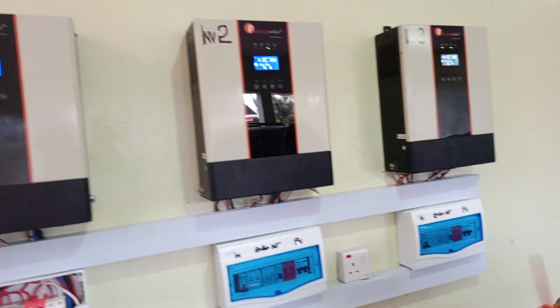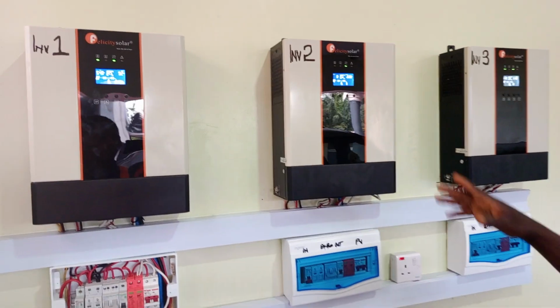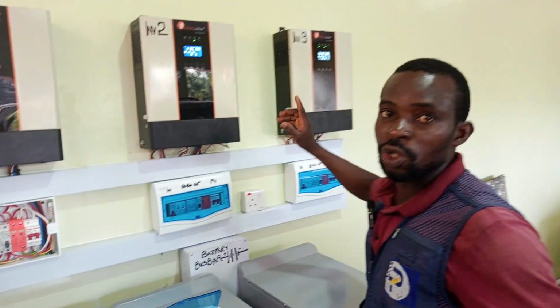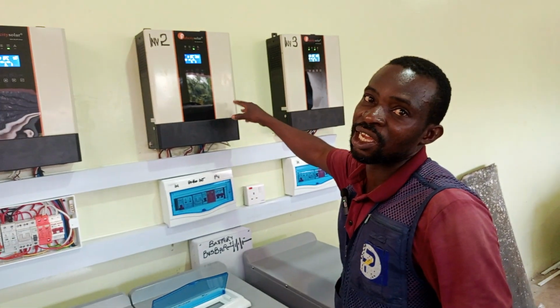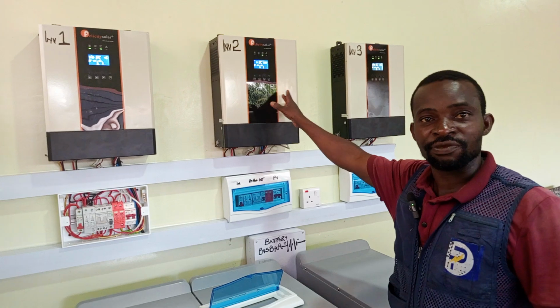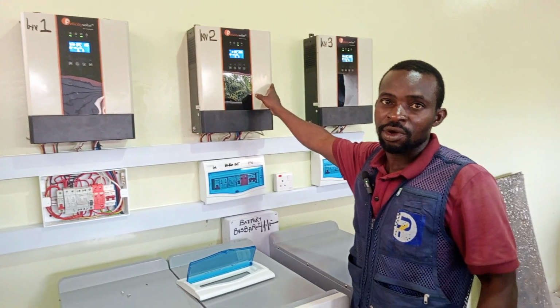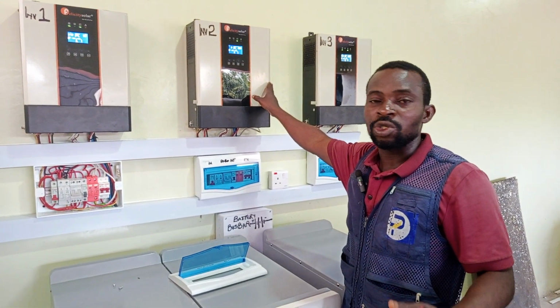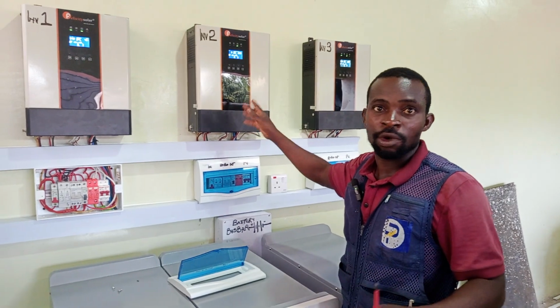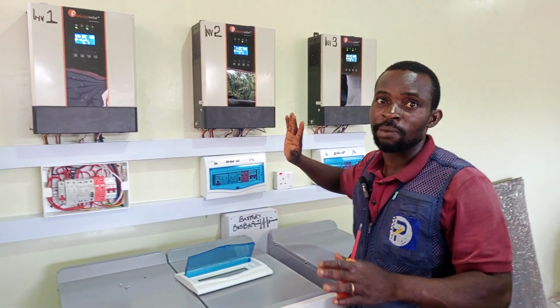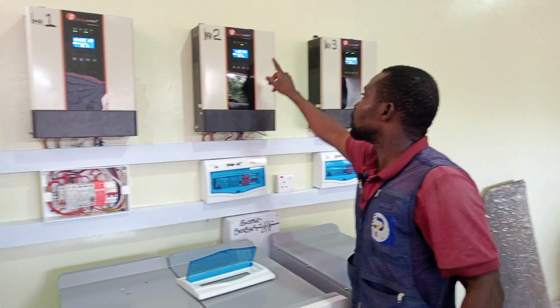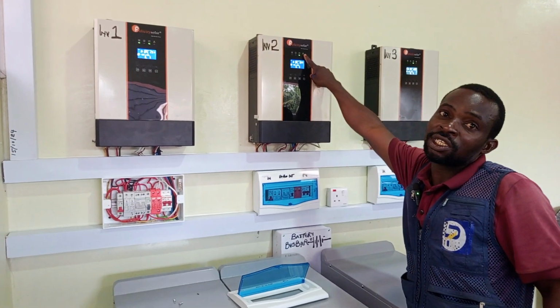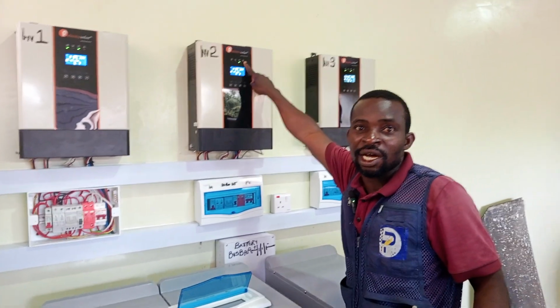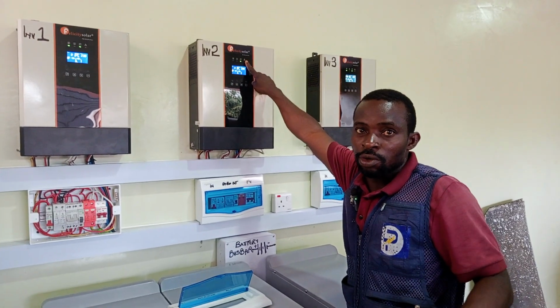But one disadvantage is that, let's say as you are running it, if there's still load and you only turn one on, and the load is more than the inverter can handle, it will show you error 45. What you need to do is restart your system, turn off your load and restart. Everything will come back to normal. So don't be scared if you see this warning signal thinking your inverter is bad - it's not, it's still working.